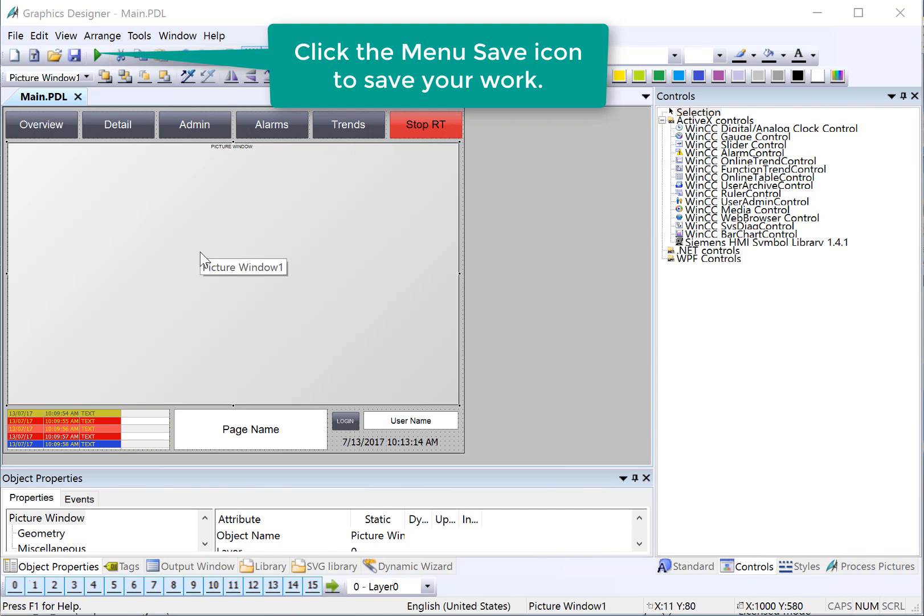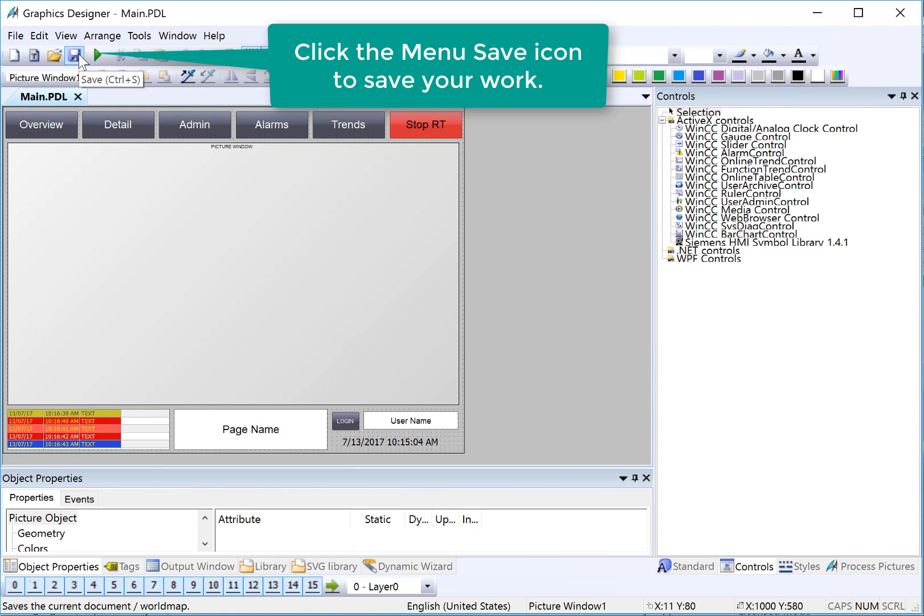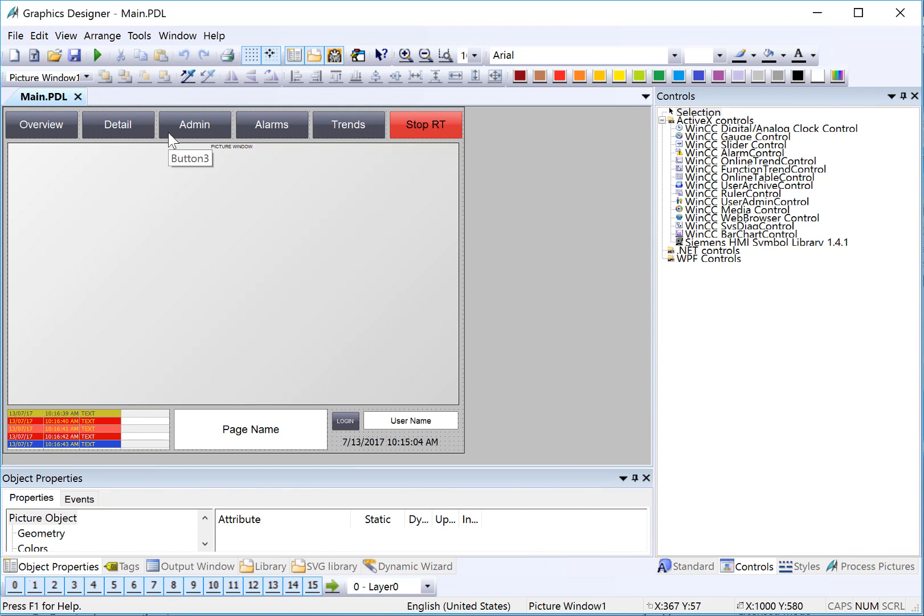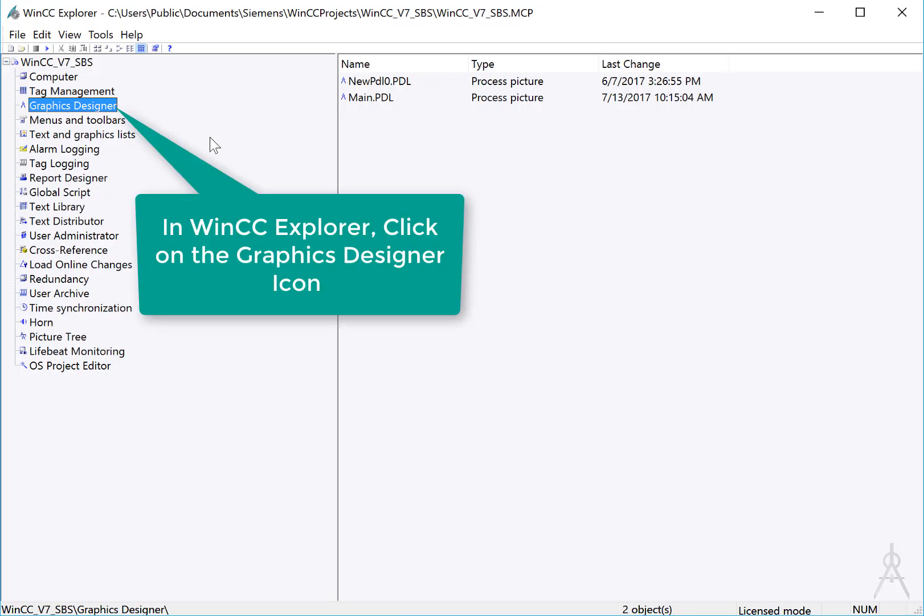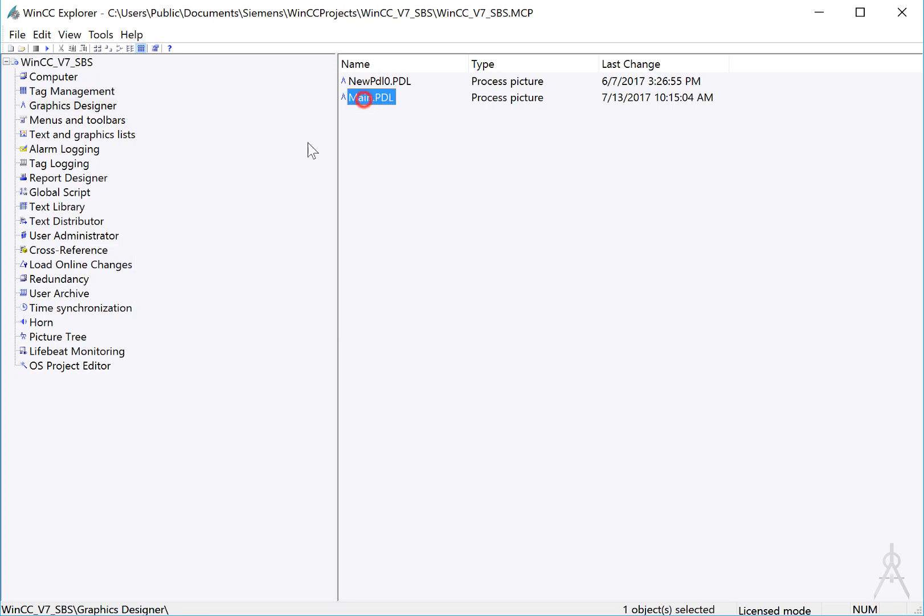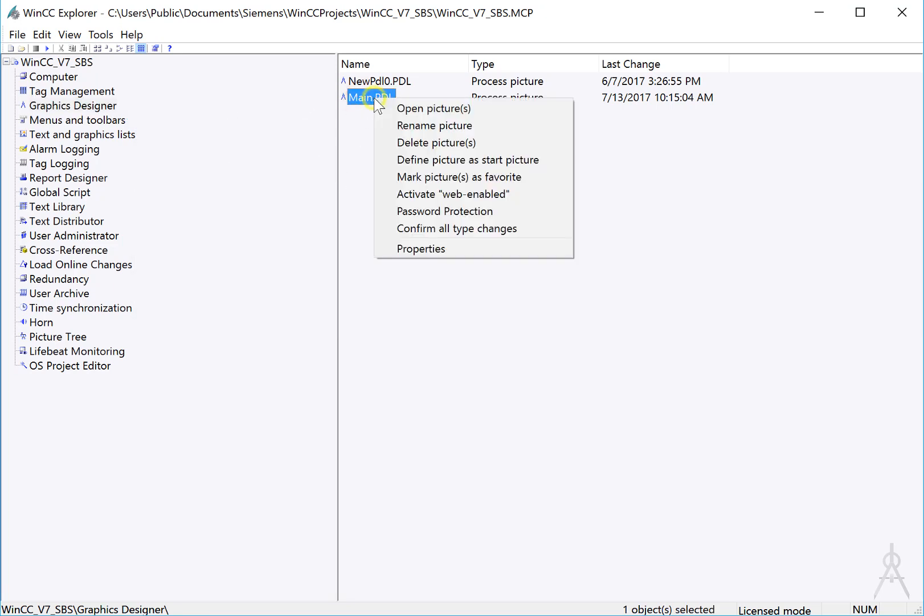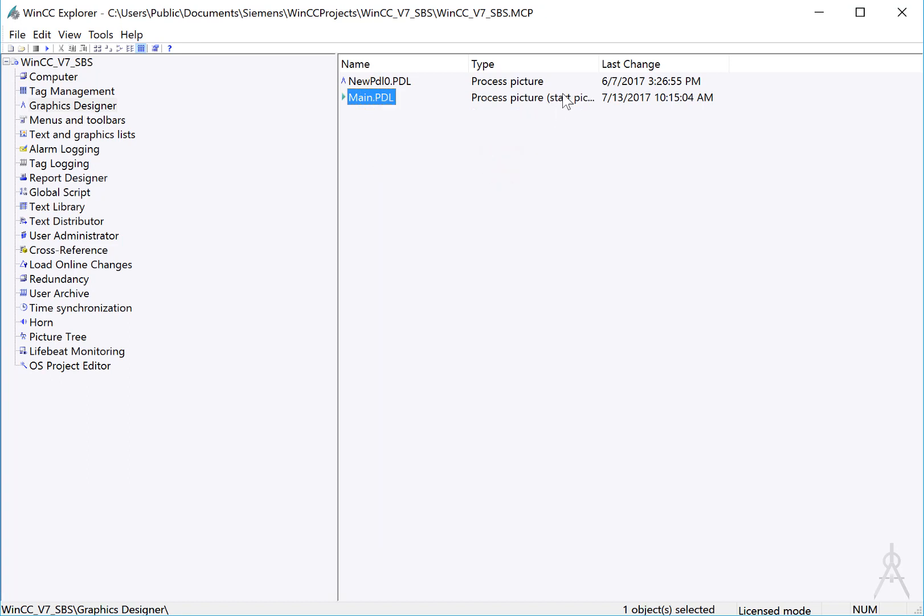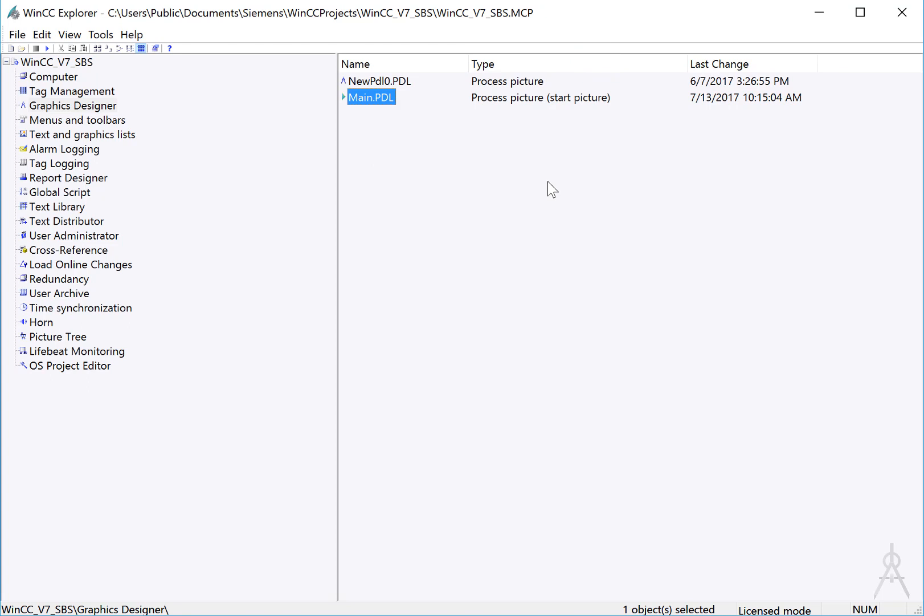Now that we have our page laid out, there's a couple of things we need to do. Most importantly, we need to save this page. So I'll just hit save. And then we want to set this as our default screen. This is going to be the screen that automatically shows when we go to runtime. And then they will show child screens in this picture window by pressing the buttons. So we're going to go back to WinCC Explorer and highlight graphics designer. You'll see that we have main PDL in our list now. I will right click that and do define picture as start picture. This will tell WinCC that this is our default screen when we go to runtime. Next up, we'll create child screens for each of the buttons.